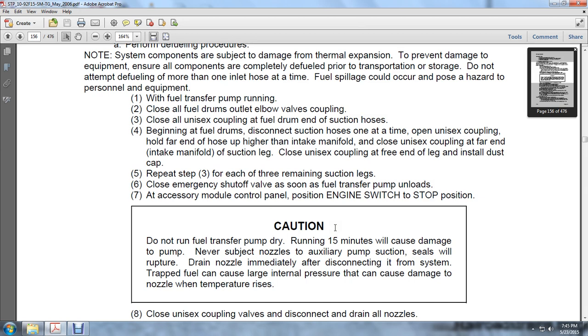Never subject nozzles to auxiliary pump suction. Seals may rupture. Drain nozzles immediately after disconnecting them from the system. Trapped fuel can cause large internal pressure that can damage the nozzle when temperature rises.